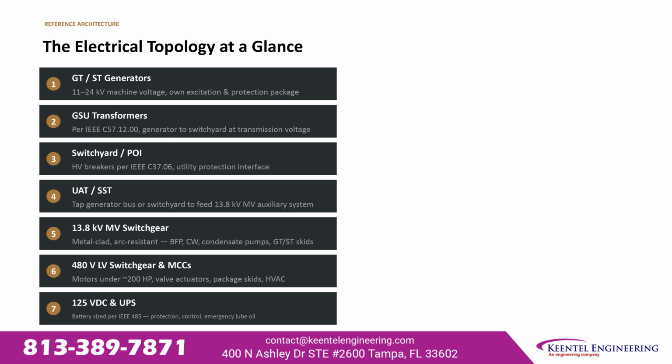C57.12.00, step that to transmission voltage for the switchyard and point of interconnection. The switchyard connects to the utility through HV breakers rated per IEEE C37.06. Unit auxiliary and station service transformers tap the generator bus or switchyard to feed the 13.8 kilovolt auxiliary system.